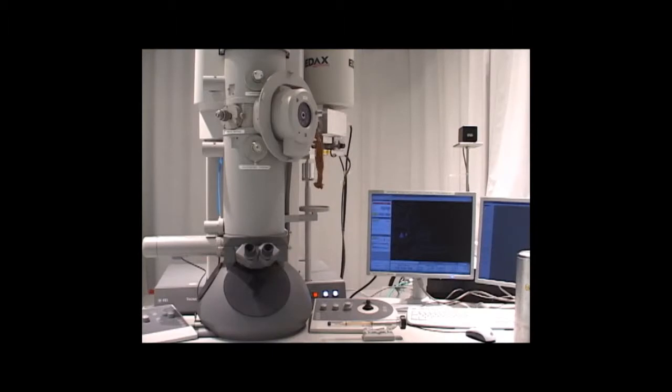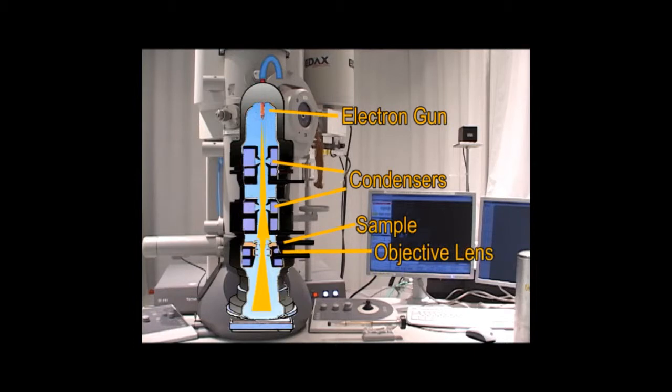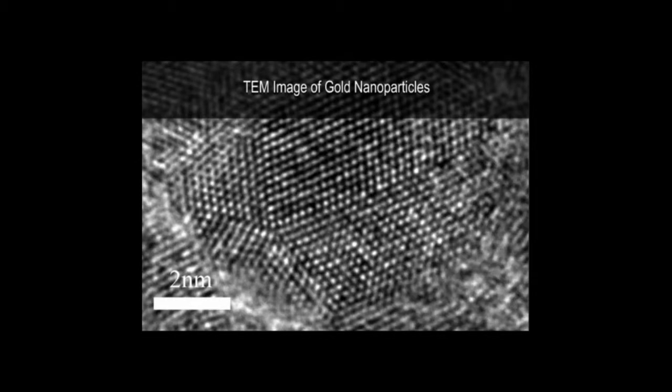In a transmission electron microscope, an electron beam from the electron gun passes through an electromagnetic condenser lens through the sample, through an objective lens, and then down to a phosphor screen or CCD camera. The condenser lens controls the size and intensity of the beam hitting the sample. The objective lens controls the magnification. TEM images show internal structures of specimens with magnification up to 1 million times, revealing structures in atomic resolution.